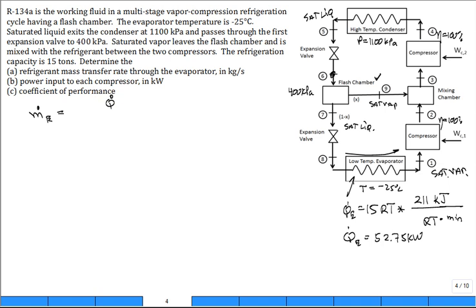M dot R equals the rate of cooling in the evaporator divided by the enthalpy change, H1 minus H8. This comes from conservation of energy around the evaporator. The power into compressor 1, W dot C1, is the mass flow rate through the evaporator times H2 minus H1. The recommended strategy is to get a table of all states and enthalpies, then calculate properties of interest.